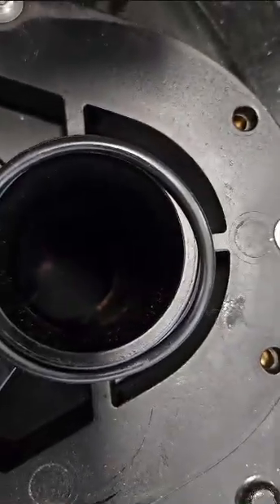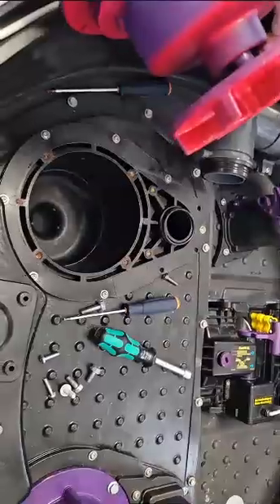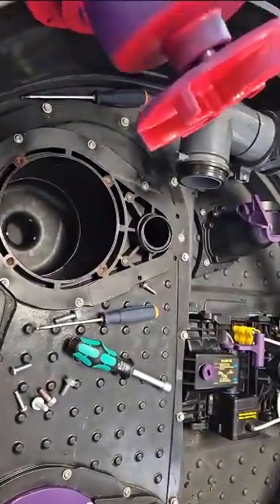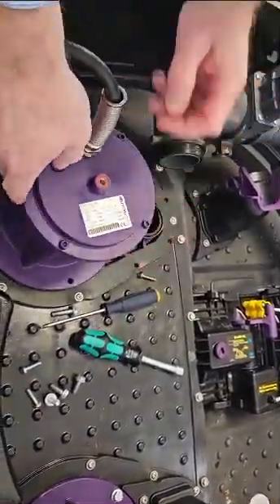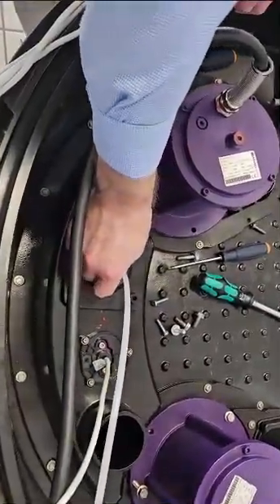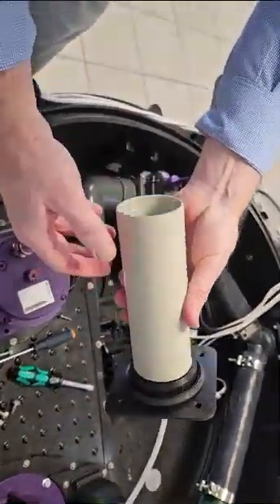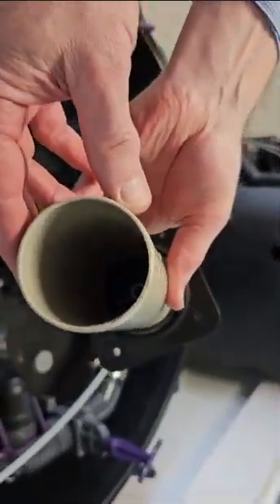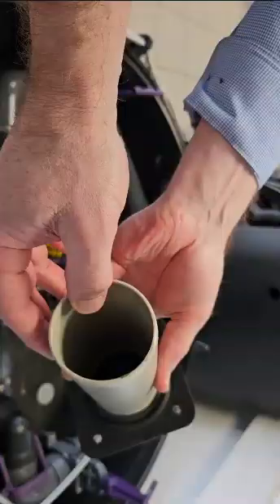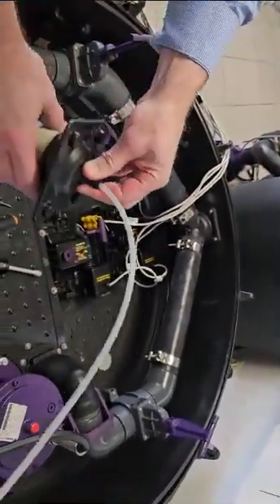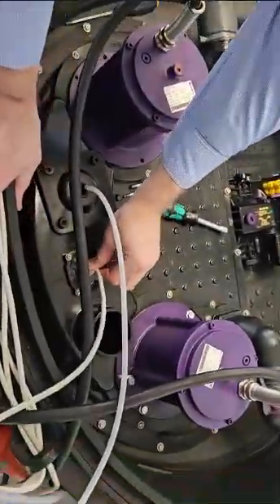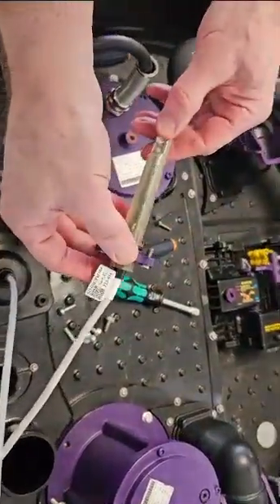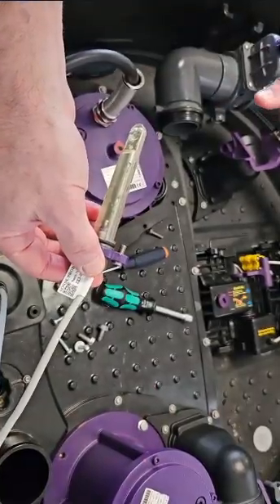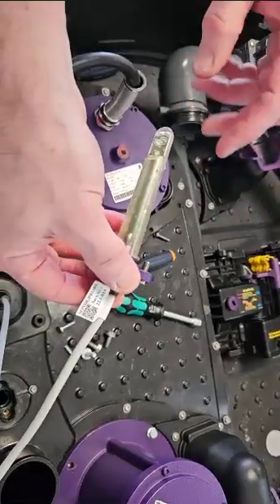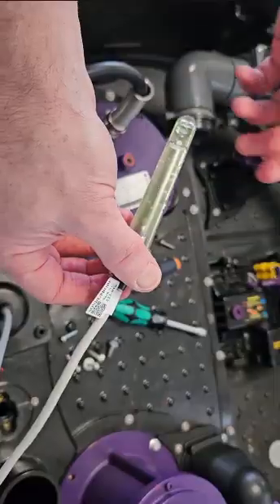We want to do a quick inspection on the impeller. This is a 6-vane cast iron impeller. The impeller should look as it does now. There should not be any wear and tear here. And again, as you see it, this is the way it should look. There can be cases where these vanes or fingers are worn, and then if that's the case, or they're not existing, they've been completely eroded, then of course the impeller, which is available as a spare part, needs to be replaced. Deep down inside here is the outlet of the pump. The pressure that the pump creates pushes the wastewater through here and out of the pressure pipe. This needs to be inspected just to make sure it's fully opened. You could see some solids in there and toilet paper. That would 100% need to be removed. So definitely a visual inspection of the pressure outlet to make sure everything is free.